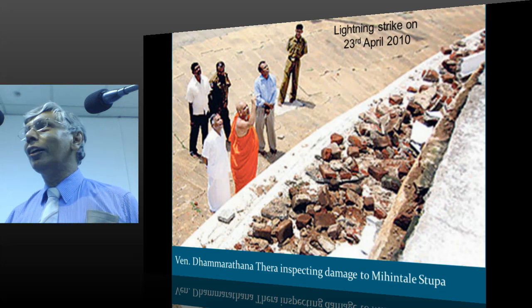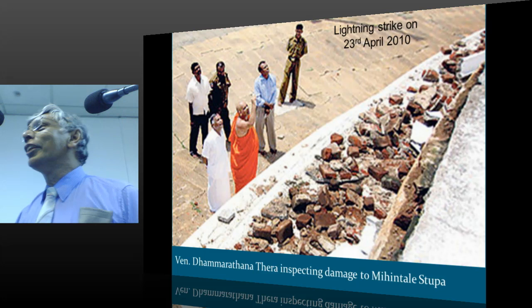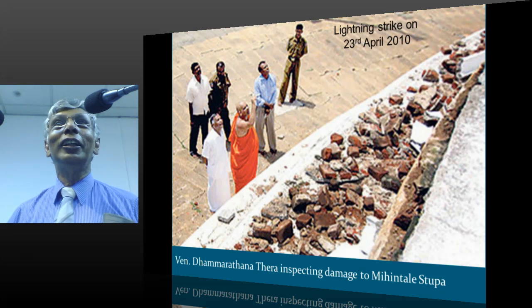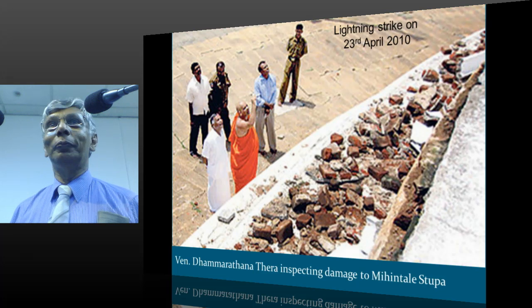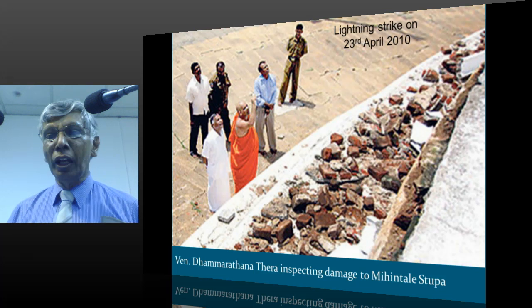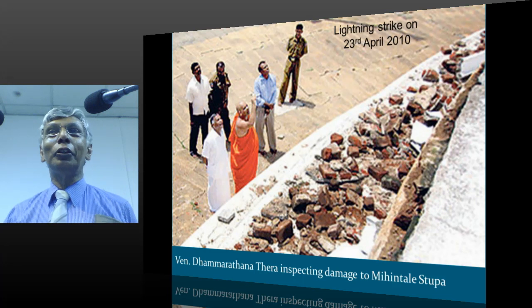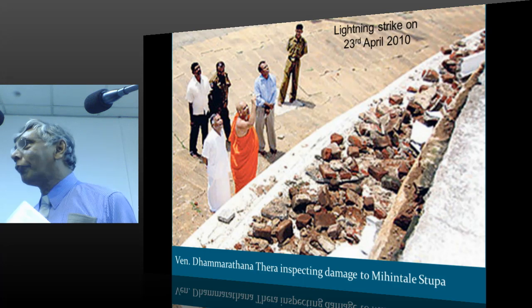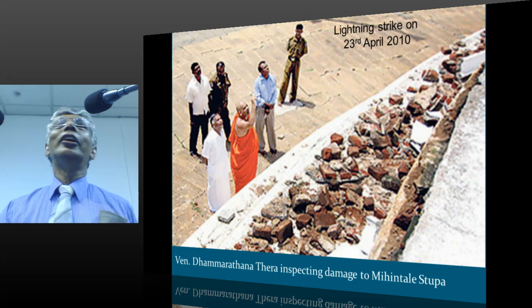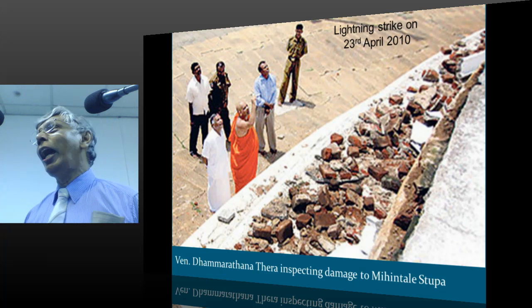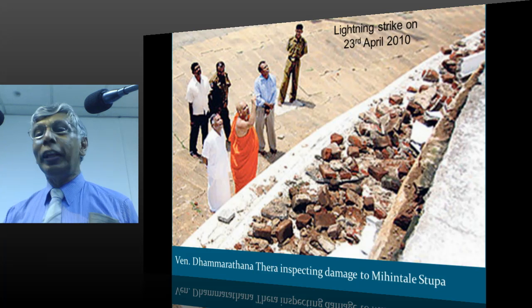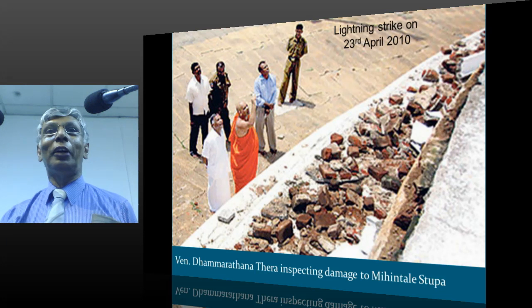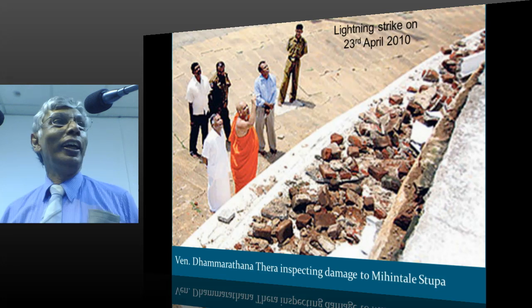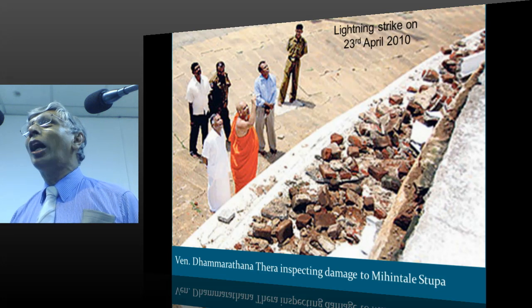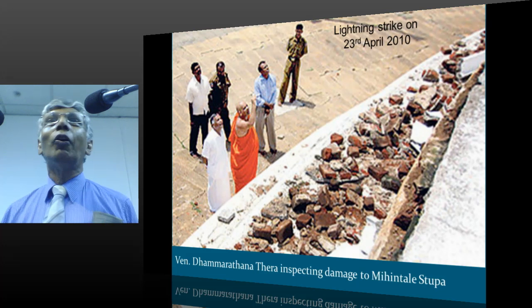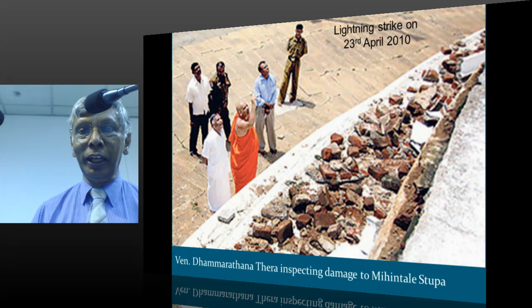You know, our people, especially those who work in the telecom industry, know the copper tapes on the towers are cut for copper. So what had happened here? Climbing this dome is difficult, but climbing up to the Pesavallu is fairly easy. The copper had been cut at the Pesavallu, and of course no one would have even thought about it. So when lightning struck, all the energy was brought down to the Pesavallu and dissipated there, and you can see what has happened. So if you do something and you don't know what you are doing, you might actually be causing more problems. That is one of the reasons why standards are very important.